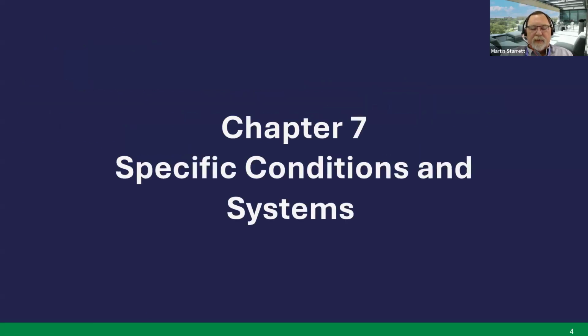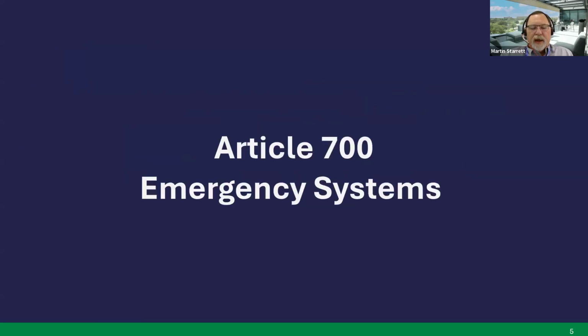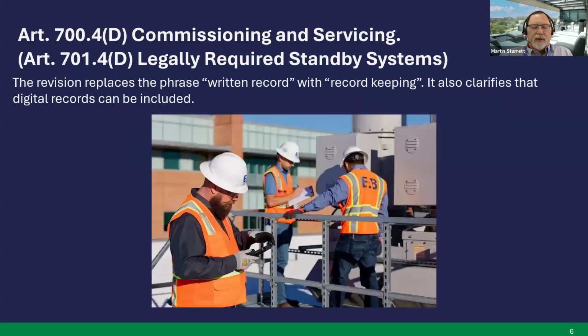All right, so today we're going to be looking at chapters 7, 8, 9, and the annexes. So we'll start with chapter 7, that's specific conditions and systems, and Article 700, emergency systems. In Article 700.4D, also the same wording in Article 701.4D in the legally required standby systems, for commissioning and servicing, the revision replaces the phrase written record with record keeping. It also clarifies that digital records can be included.